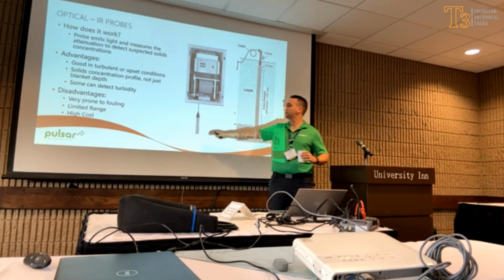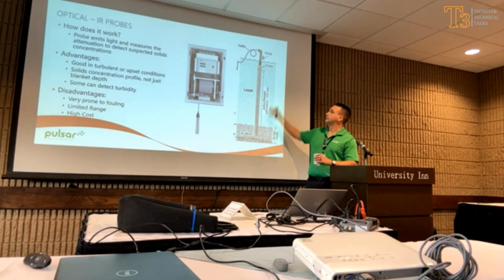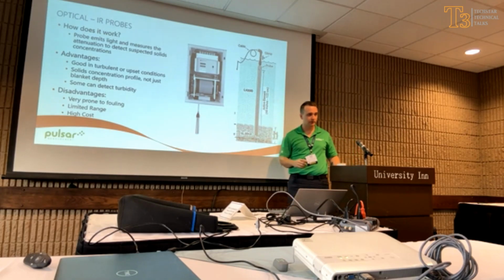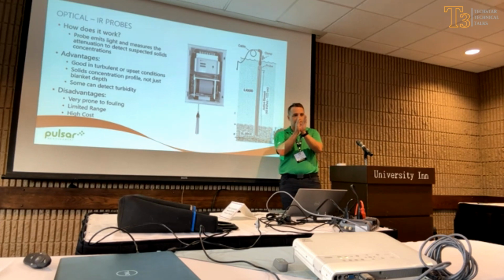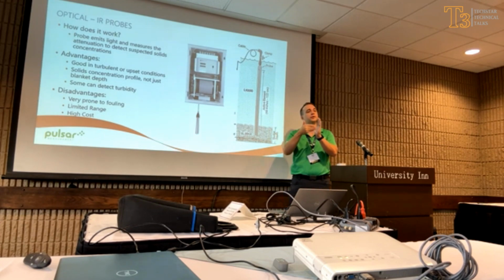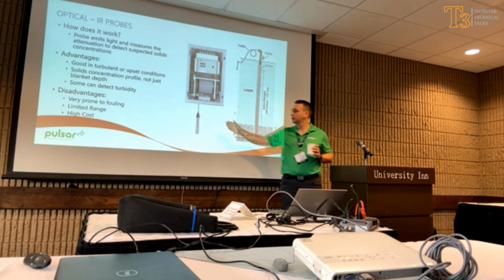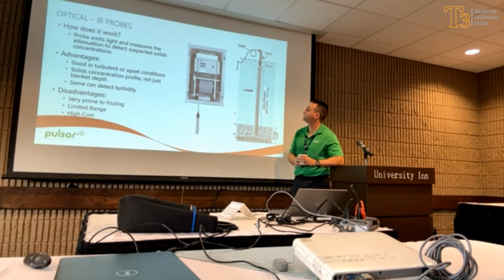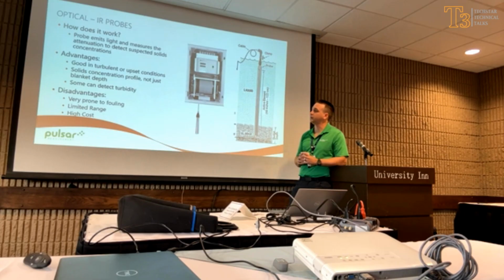So there's this probe style, and there's also what I'll call a light bar or lightsaber style, which is inserted all the way down the tank with two different halves to it. There's a teeny tiny gap that the light is continually reflected through. Rather than dropping the probe in every so often, this lives in the tank all the time, but it exacerbates the maintenance hassle. It's definitely something to think about if you're evaluating continuous measurement. This is going to be something you want to dedicate time to.